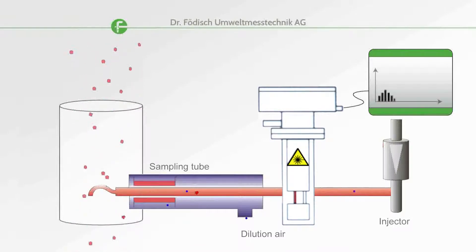The resulting mixed gas is heated at a defined temperature within the sampling tube. The injector sucks the measuring gas through the measuring chamber having the optical sensor inside. Its measuring values are compensated by the measuring values for temperature and flow. The control unit shows the dust concentration in milligrams per cubic meter in operation.